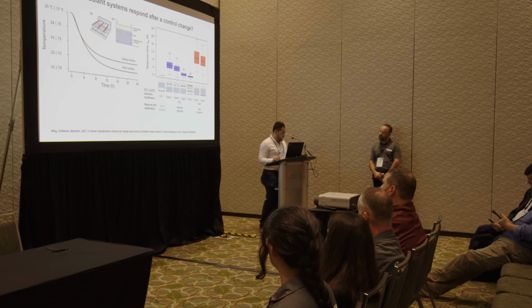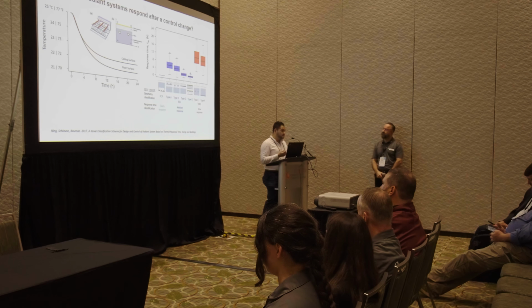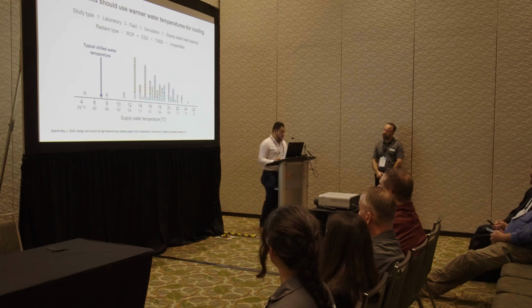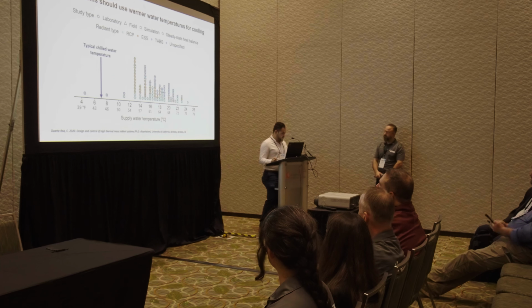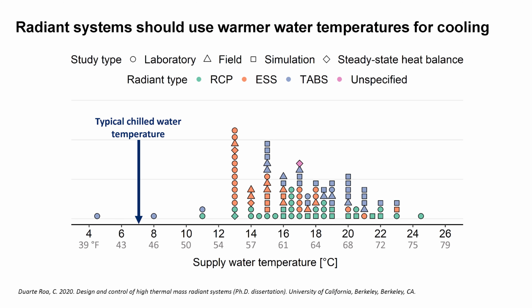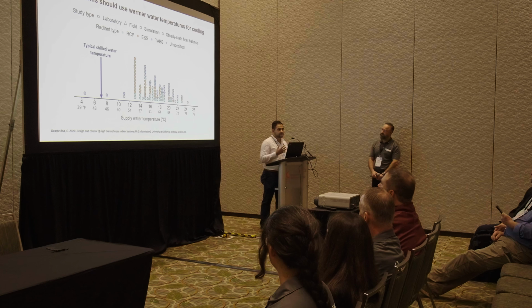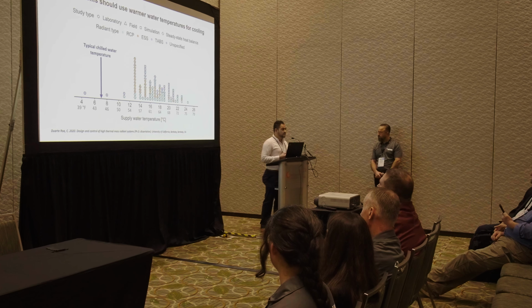However, these long response times after a control action present challenges for control, but they also open up opportunities for innovative designs and control options. In addition, radiant systems can do high temperature cooling, as Saeed mentioned. That is, using chilled water that is warmer than typical. This is possible because these systems have large heat transfer areas, sometimes involving both the ceiling and floor surfaces, as in the case of TABS systems. As you can see in this plot, various studies have shown that radiant systems can use chilled water that is warmer than 45 degrees Fahrenheit, which is the typical temperature for conventional all-air systems. However, they're not always designed to do so.